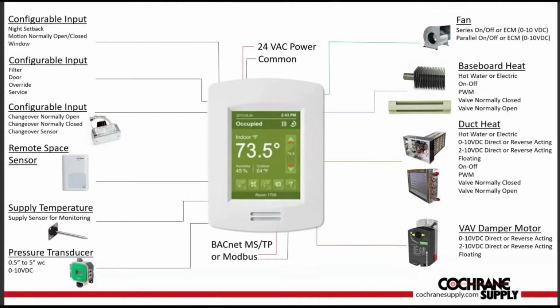The 8250 can be configured to operate a series or parallel fan with on-off or ECM motors. If you've got reheat, either baseboard or duct heat, hot water or electric, the 8250 offers several options. With a VAV or VVT install, there's going to be a damper motor, so pick one of your choice, either modulating with a VDC output or floating contacts. Just to reiterate, one part number has all of this configuration flexibility.